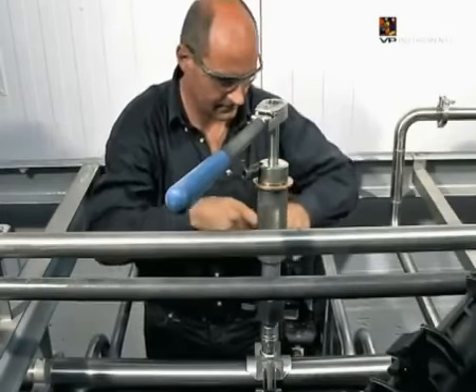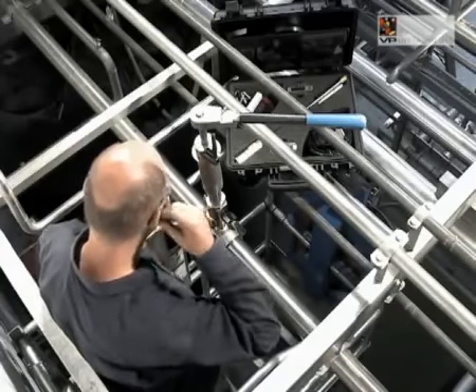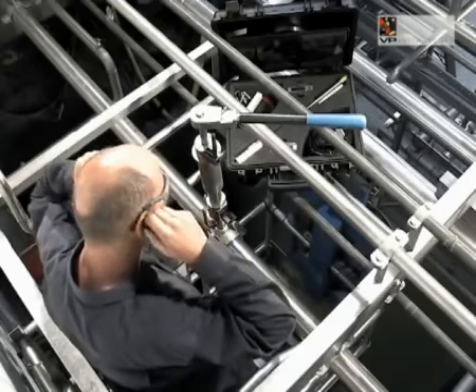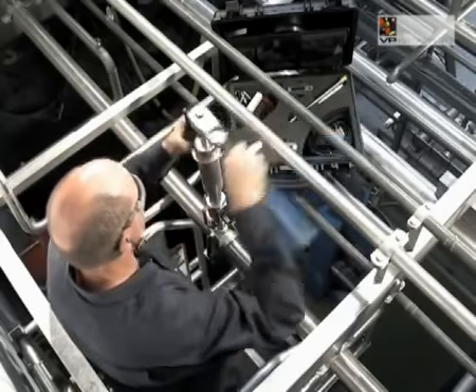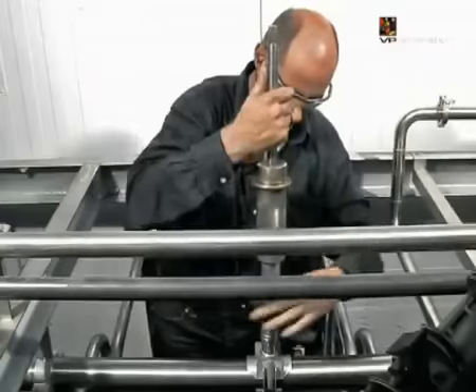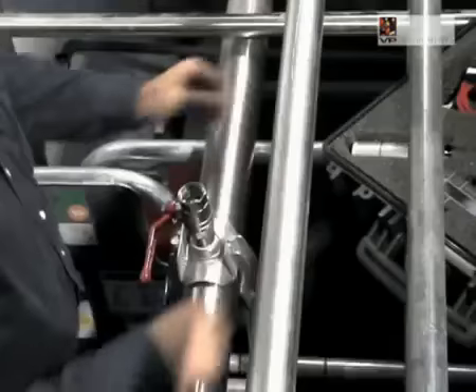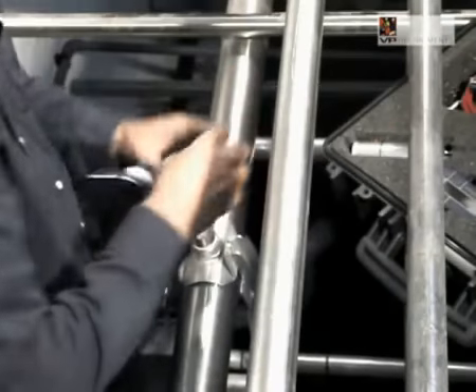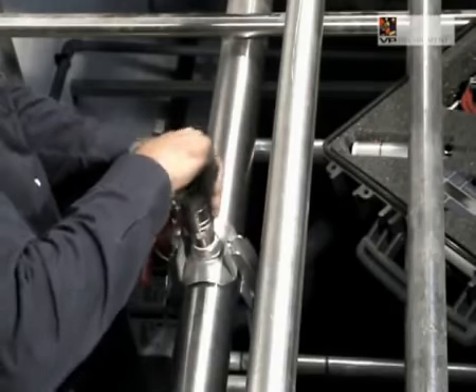Determine the inner diameter of the pipe. The VPFlowScope can be installed using a socket or hot tap saddle. Hot tap saddles can be installed on pressurized pipes. Hot tapping is work for trained technicians. It requires special equipment. This equipment is not delivered by VP Instruments.